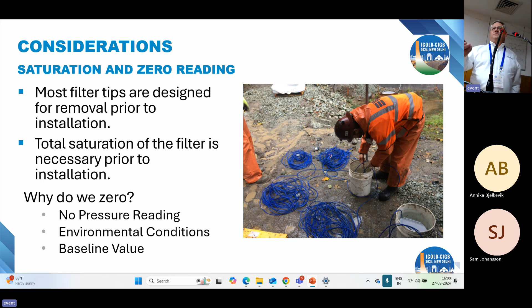There are two methods to zero, and I apologize, it's a lot of words. The first method, ideally, if you know the water level in the borehole, is to put your piezometer just above that water level and take a reading. That would be the closest zero you can get to that surface. You want to do that because you don't know what elevation you are at. All the manufacturers do a zero calibration at their facility. But for example, where we are in New Hampshire, eastern U.S., we're 500 feet above sea level, whereas here you may be 5,000 feet above sea level. That may very much change the way the zero reading happens. So that's why we do the zero.